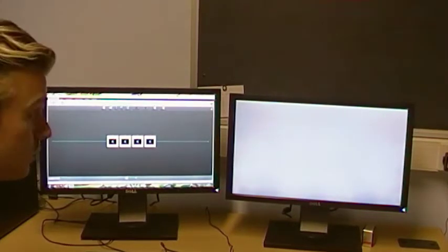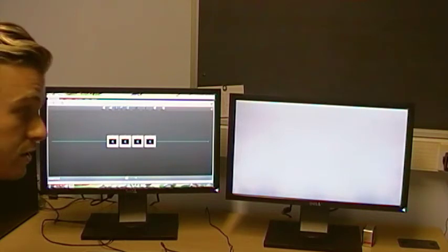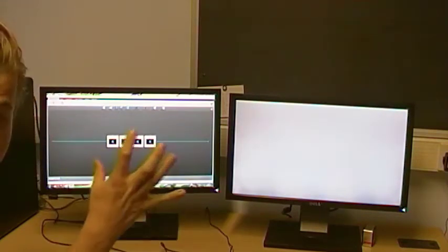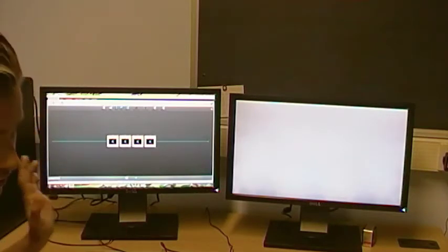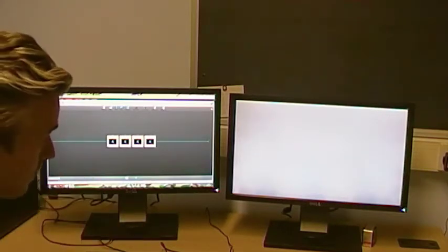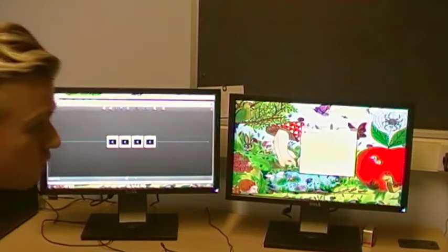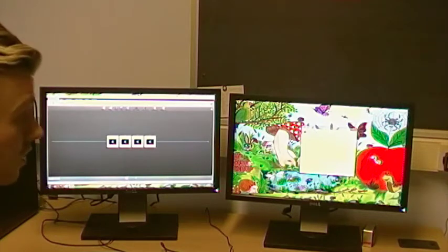And then what this does is load up the calibration procedure. Now for infants this will be where you see 5 animations in 5 corners, 4 in the corners of the screen and 1 in the middle. This is so that the eye tracker can calibrate to the specifics of the participant's eyes that you've got. So what you'll do is you'll show an interesting animation in those corners to grab the participant's attention, so the eye tracker knows that that's where the participant's looking at that time.